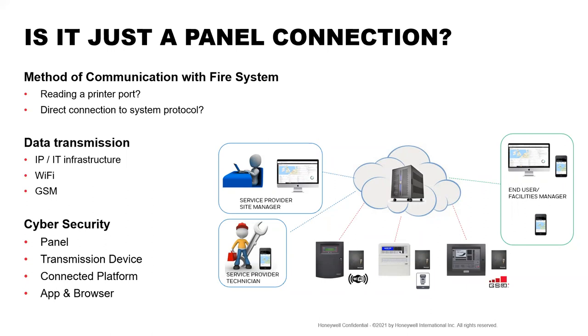With a direct connection to the system protocol, which is the language that the system's speaking, the connection will become part of the makeup of the system. We're now communicating directly with the devices, the panel loops, the loop cards, the panel controls, and all that kind of stuff. Using this connection method gives a range of detailed system events, control options, commissioning options, and we're there with that word again, compliance testing, basically. So you can choose how much of this that you use or not on that particular system.